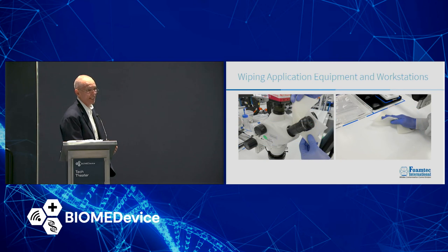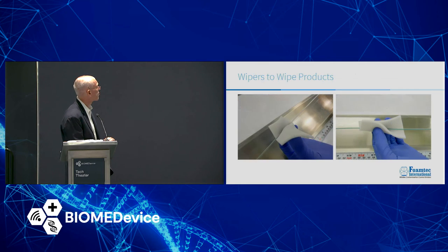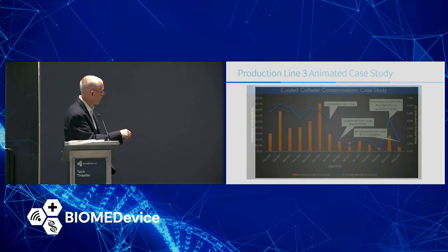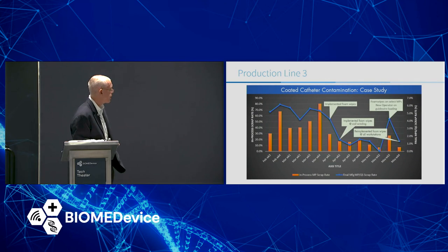We found a lot of contamination on the microscope. They had been using foam to wipe down the device for the previous 5 or 6 years, so this wasn't a change. So let me walk you through this chart.